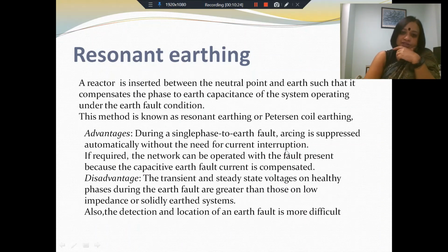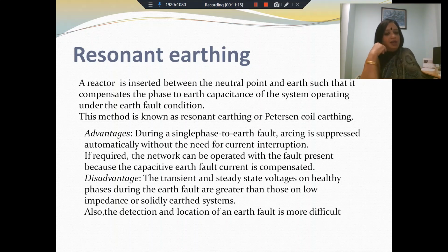And then we have resonant earthing. In this resonant earthing, we do have a reactor. Similar to the second scenario, you have a reactor which is inserted between the neutral point and earth, and it is so chosen that the reactance of this reactor is equal to the phase to earth capacitance of the system operating under earth fault condition. So under earth fault condition, the phase to earth capacitance of the system is considered, and the reactor has a reactance which is equal to this capacitive reactance. So therefore, you have resonant conditions under fault conditions only. This method is known as resonant earthing. It is also known as Petersen coil earthing, after the innovator.